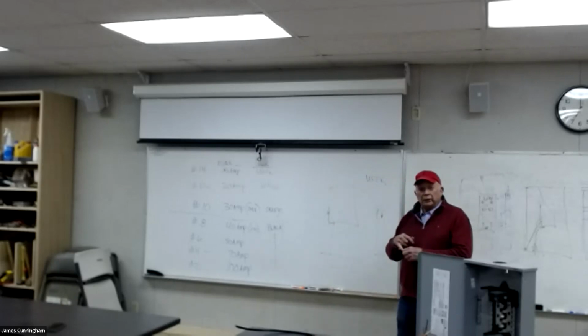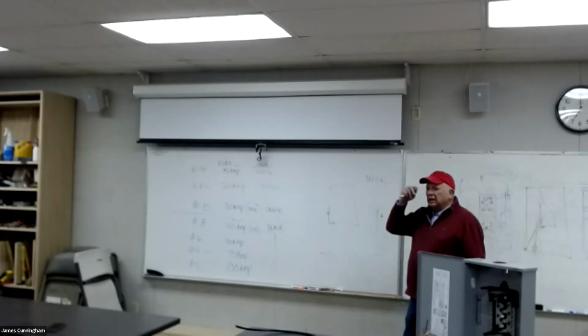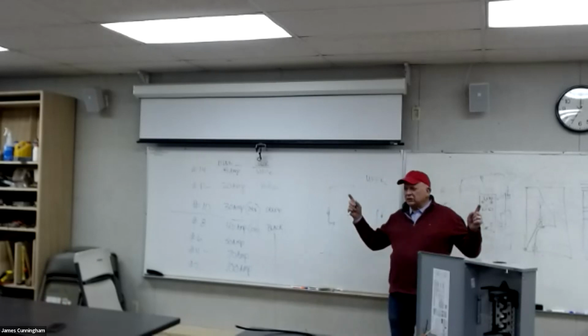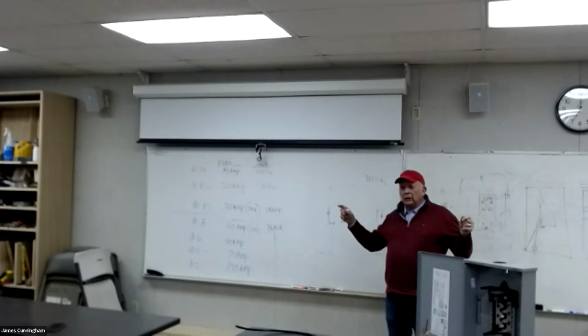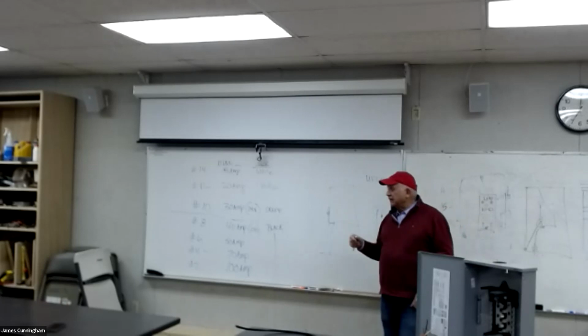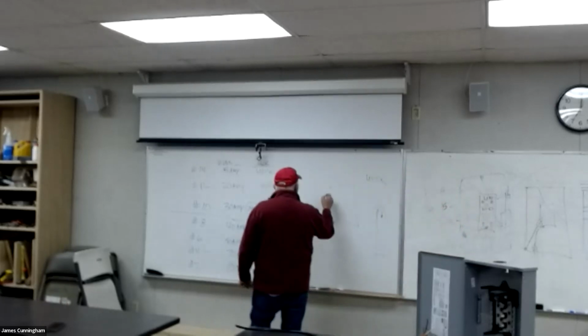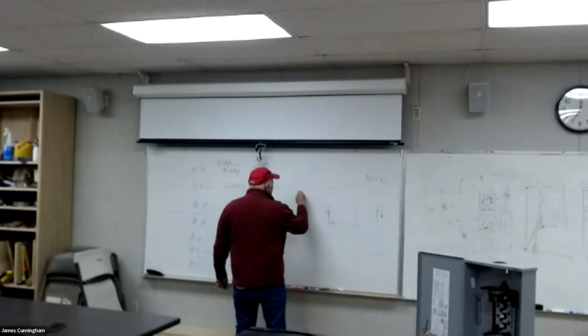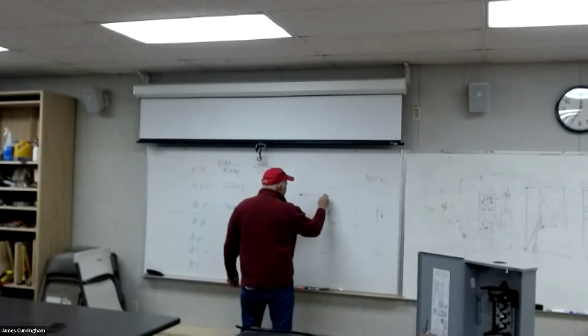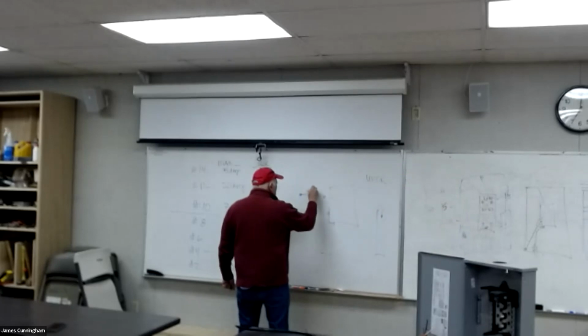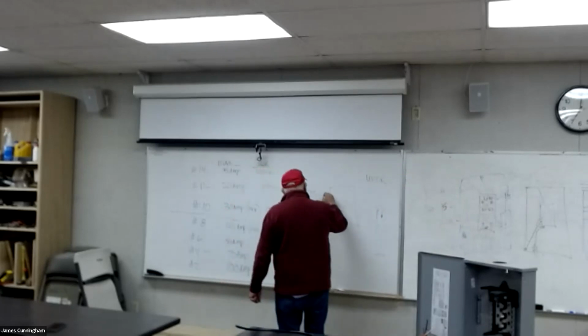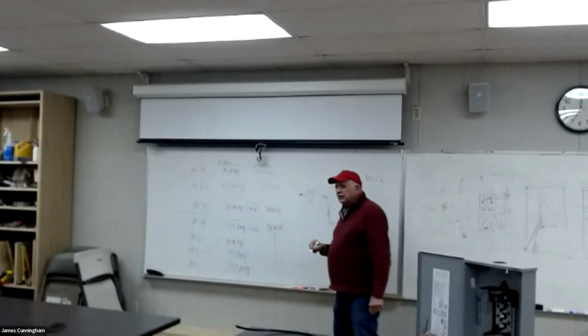So I have to have both. I have to have a cold water ground, and I have to have either a grounding rod, which is an 8-foot copper rod that's driven into the ground. Here in Santa Barbara, if you're going to do a 200 amp service, a lot of times they're making us do 2 grounding rods, and they have to be at least 6 foot apart. The wire has to be continuous. So if I had 2 grounding rods, I'd put one in here, put a clamp on it, put another grounding rod in here, minimum 6 feet, and then I'd run that to my grounding bus bar in the panel.